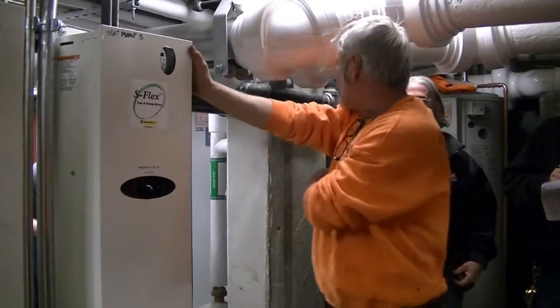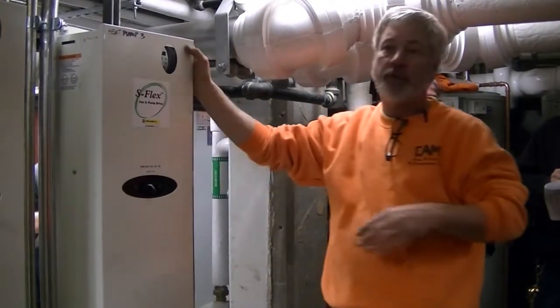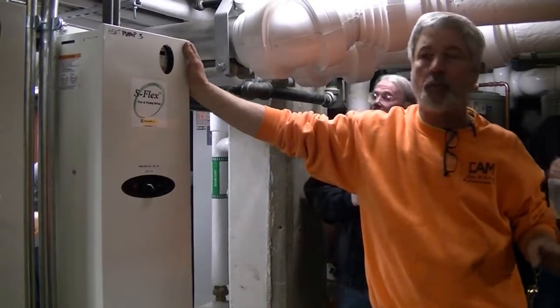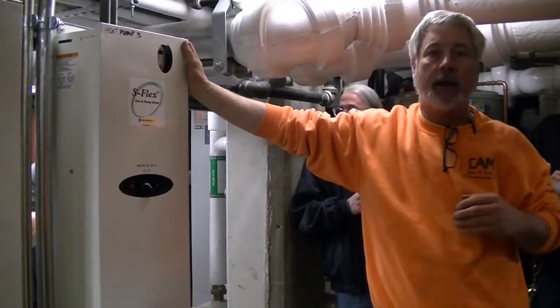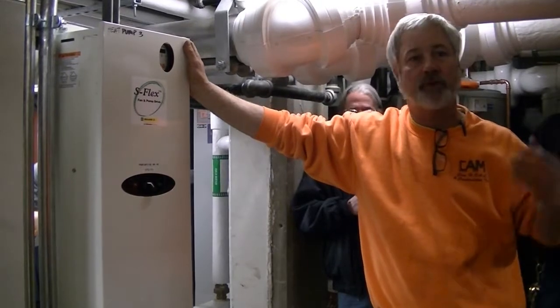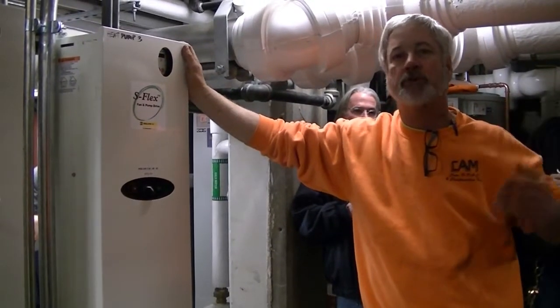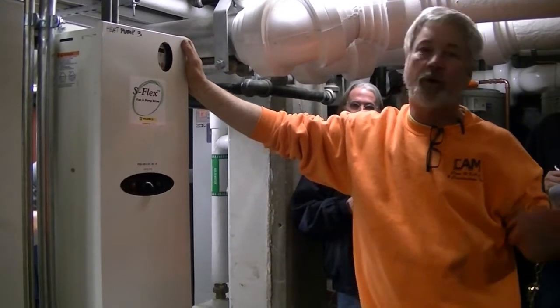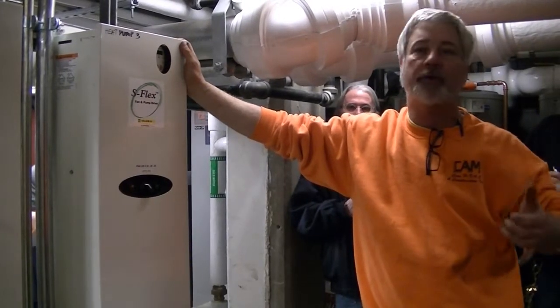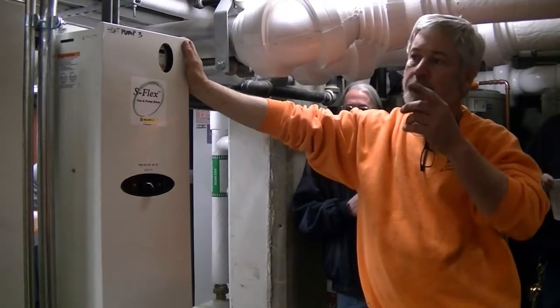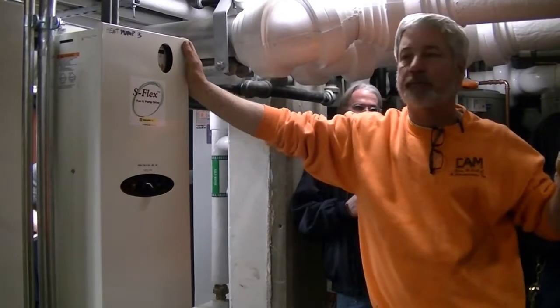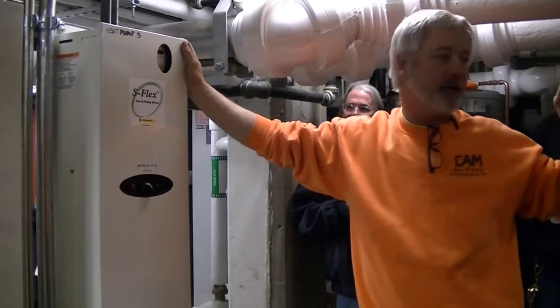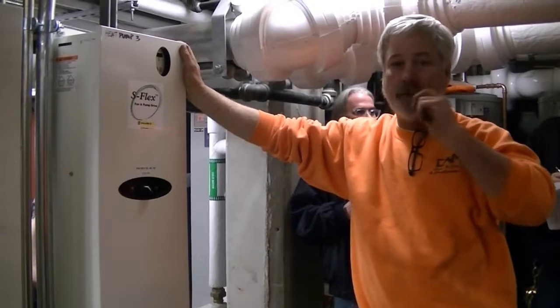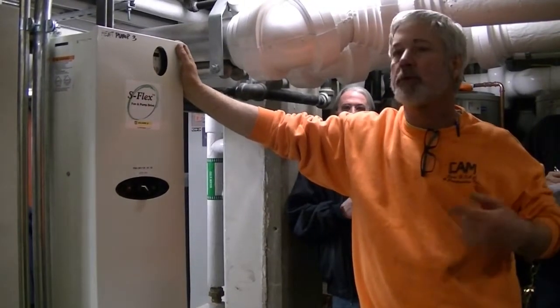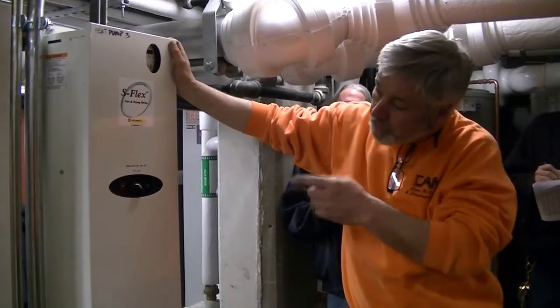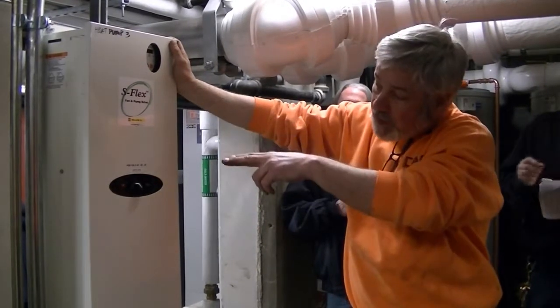The heating plant does 2 different things. It heats the domestic hot water, which is behind me, and it also heats all the heating water for the building. It has a reset program in it, so the heating pipe temperature is not always the same. It offsets according to what the outside air temperature is. We have independent pumps for each one of the appliances, meaning the cogen, and each one of the boilers has its own pump to force water through that appliance. And then the building main heating pumps are over on the other side.